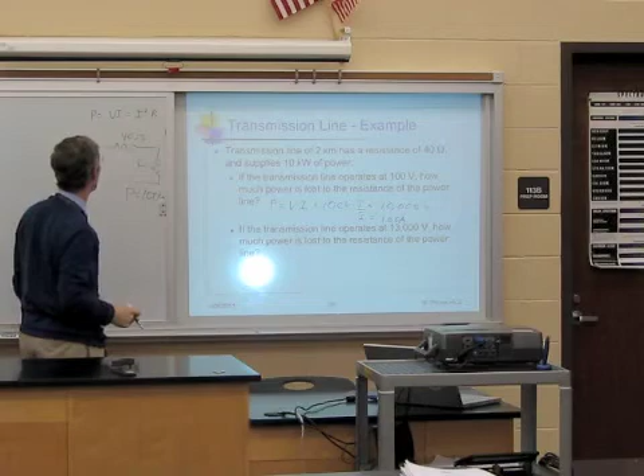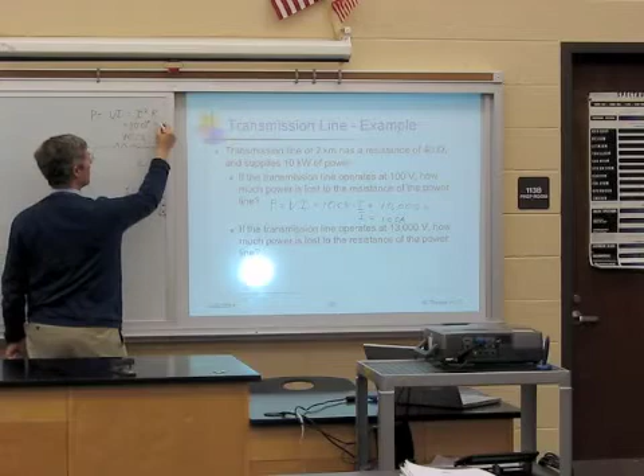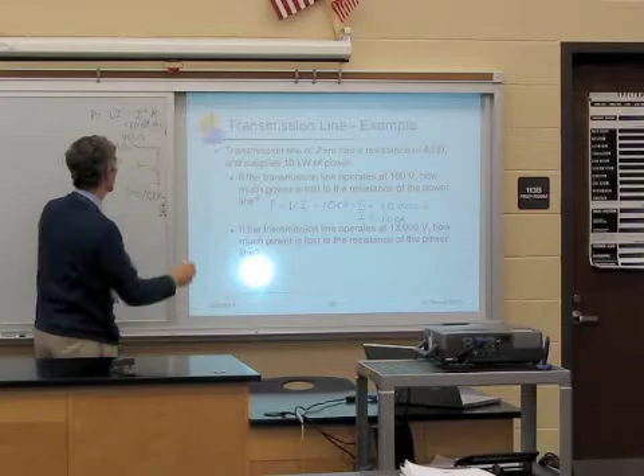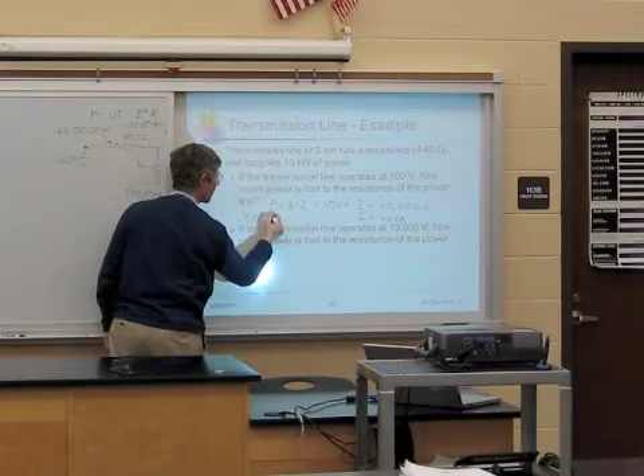How much power will we dissipate in this 40 ohm resistance? We can use I squared R, or V squared over R. With 100 amps flowing through, that's 100 squared times 40, which is 10,000 times 40, so 400,000 watts — 400 kilowatts — dissipated just to deliver 10 kilowatts to the load.